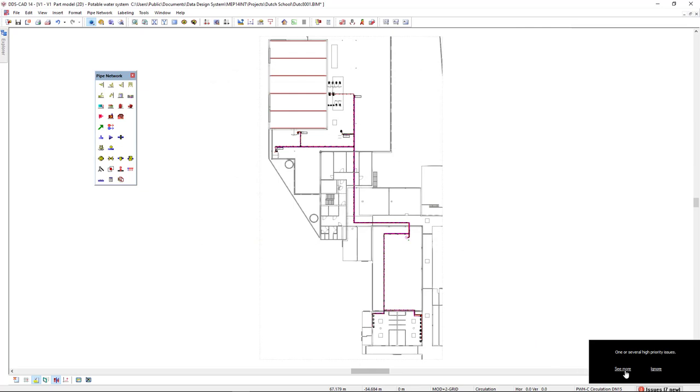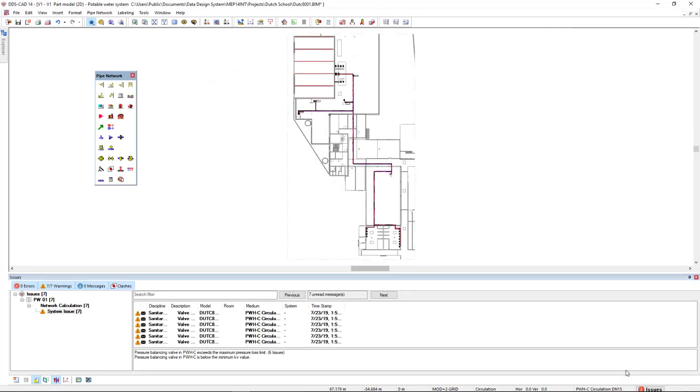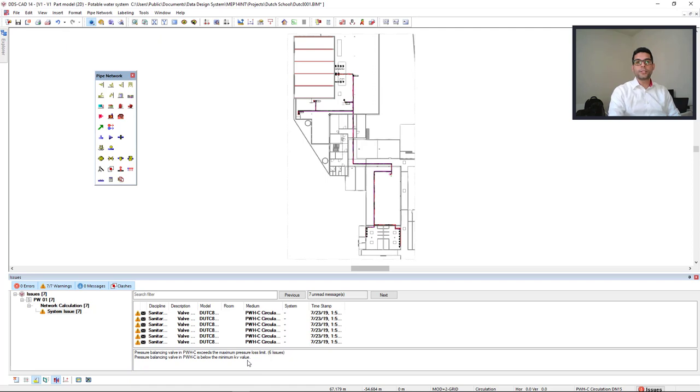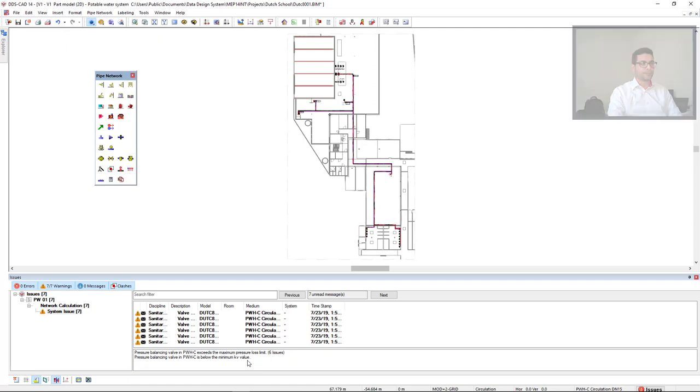So by clicking on see more, we see here several points in which the pressure balancing valve exceeds the maximum pressure loss limit. And also, it is displaying that the pressure loss is below the minimum KV value. With this information, we know what to do to optimize our model.